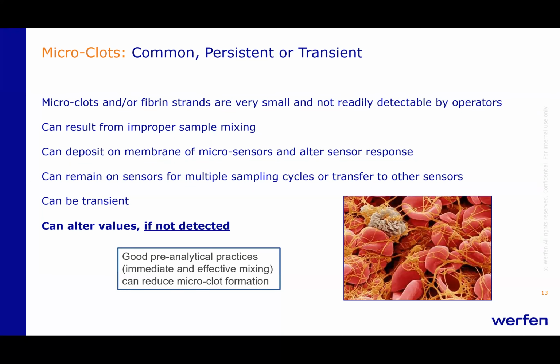So microclots can be common, and I'll show you some data on that, persistent or transient. In other words, they can wash away and they might not be detected. Microclots and/or fibrin strands are very small and not readily detectable by operators. In other words, you cannot visually detect microclots. They can and do result from improper sample mixing, and I will talk about best practice for sample mixing. They can deposit on the membrane of microsensors and alter sensor response. They can remain on sensors for multiple sampling cycles or transfer to other sensors, and they can be transient. And they can certainly alter values, as you saw from that study, if they're not detected.